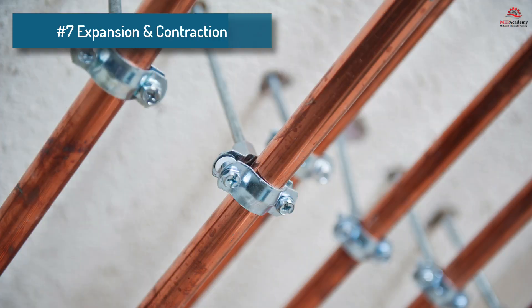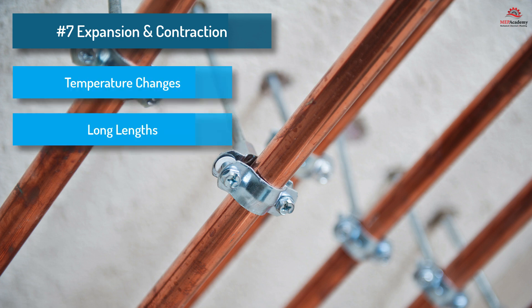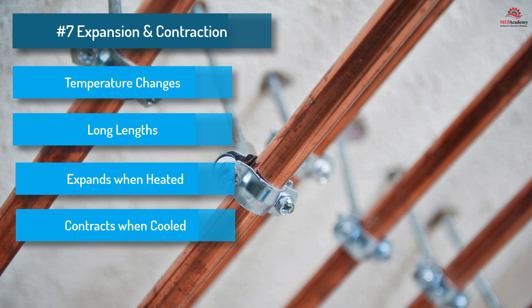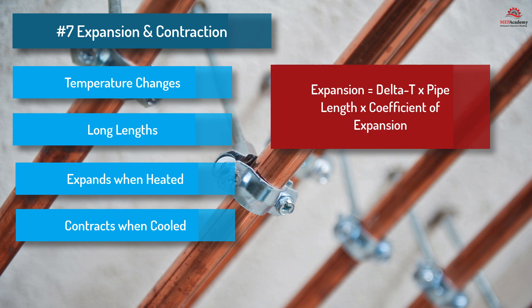7. Expansion and contraction. The refrigerant piping should be designed to accommodate the expansion and contraction of the piping due to temperature changes. Long lengths of piping can cause problems when temperatures vary, as the piping length will grow when heated and contract when cooling down. Some method of compensating for this expansion and contraction must be considered. Copper piping expansion equals delta temperature in piping times piping length times coefficient of expansion.